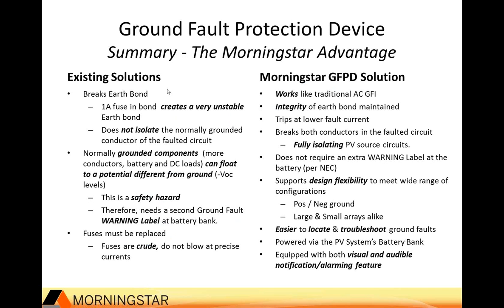So to summarize the differences, with the existing solutions, when that fuse blows, it breaks the earth bond. Okay, now you've basically taken your ground and removed it. So you've broken the bond that is supposed to be in place. Normally grounded components can now float to a potential difference from ground, potentially a negative difference. That's a safety hazard, and you've detected the ground fault, but you've put it into a less safe state than it was in before. Also, these fuses are not exactly precision devices. They're a bit crude. They don't blow at specific levels. In some cases, you can have a ground fault exist and not have enough current to trip or blow that fuse.